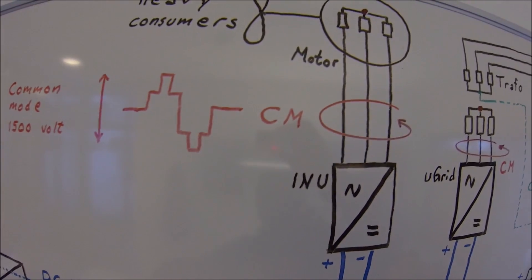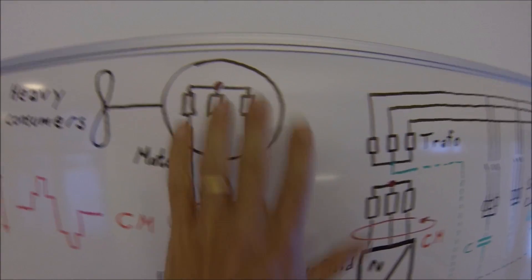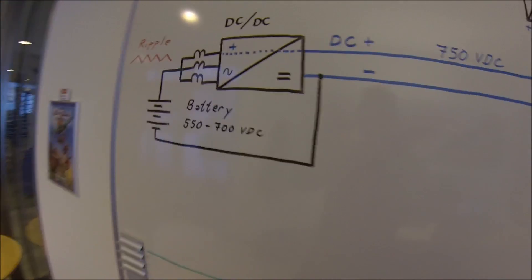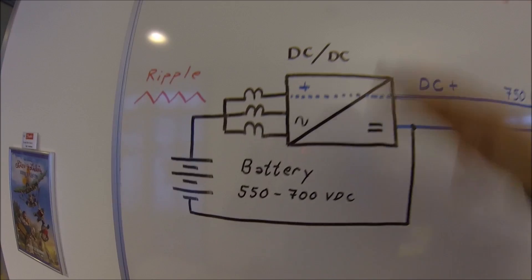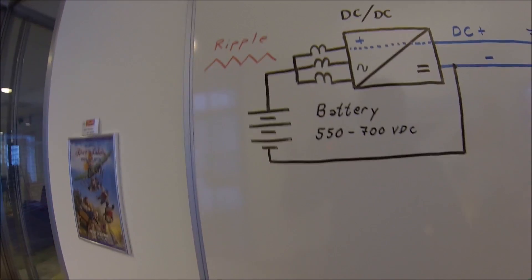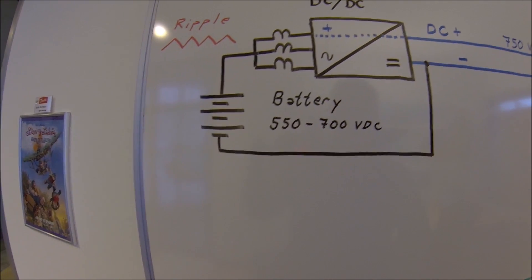You know, this common mode which you can see in our oscilloscope doesn't make any harm here on a motor, it doesn't make any harm here in a transformer or in this transformer. But if you do this to your battery, you probably will have problems with your battery management system. And here comes a challenge.